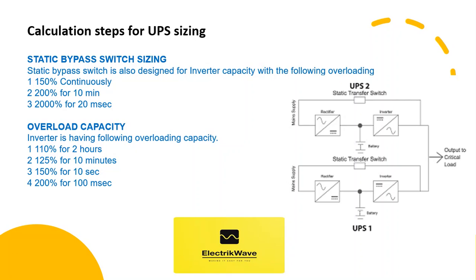Static bypass switch sizing: the static bypass switch is also designed for inverter capacity with the following overloading — 150% continuously, 200% for 10 minutes, 2000% for 20 milliseconds. The inverter has the following overloading capacity: 110% for 2 hours, 125% for 10 minutes, 150% for 10 seconds, 200% for 100 milliseconds.